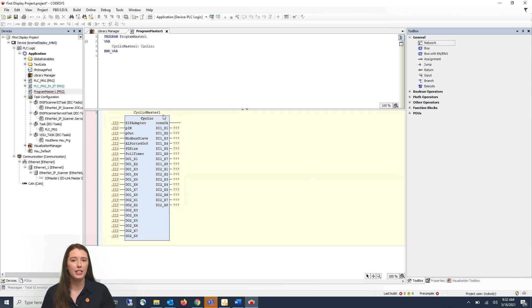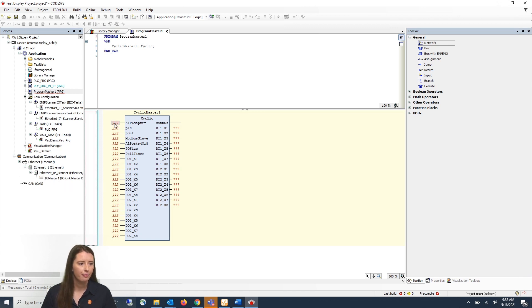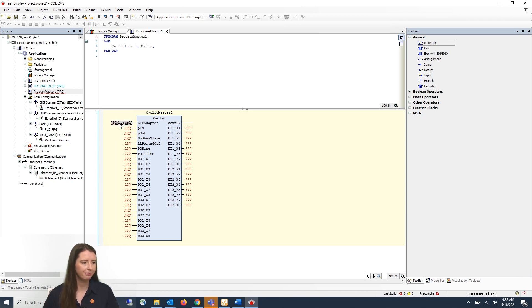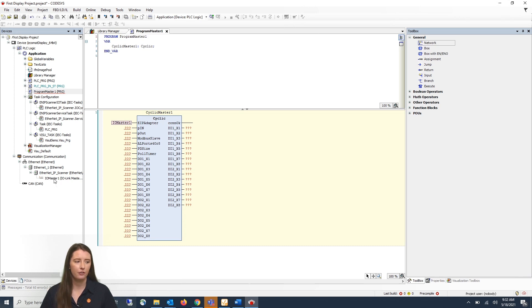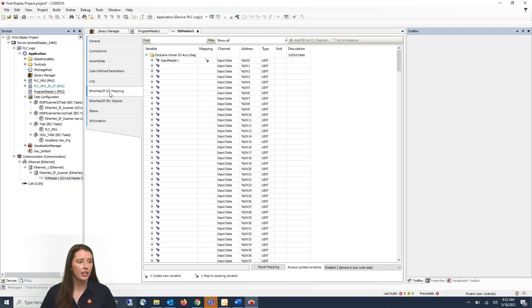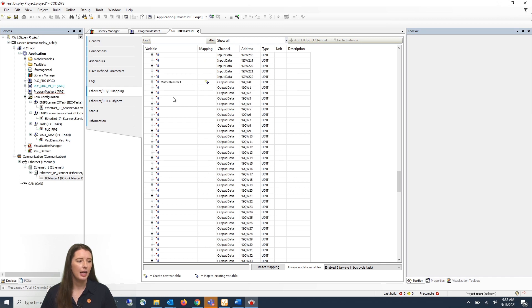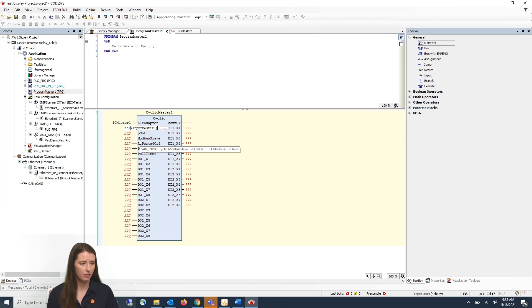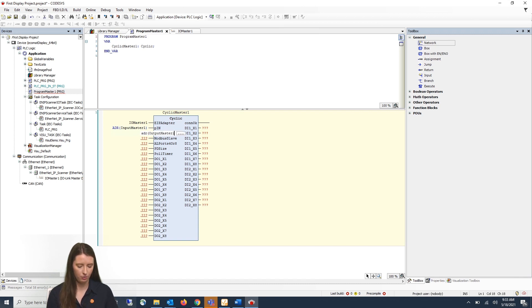Now that our function block is added let's assign the appropriate variable names. First we have the Ethernet IP adapter which is going to be the IO-Link master name that you gave under the Ethernet IP scanner. So for this video it is IOMaster1. Next you have the pointer to your input and output arrays which is the variables that we gave in the previous video which you can find here. If you double click on your IOMaster and go to Ethernet IPIO mapping you'll see that I named them inputmaster1 and outputmaster1. So if we go back to the function block you will do ADR parentheses inputmaster1 and ADR parentheses outputmaster1.